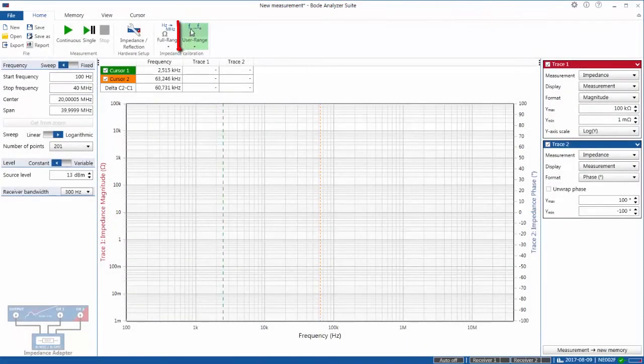So now you can see that now that you have calibrated, this area has gone green to show that it is actually calibrated. Let's do a measurement to see if you read 100 ohms. Yes, we do see 100 ohms, and the phase is zero, so it's measuring correctly, so that gives me confidence that the device has been calibrated properly.